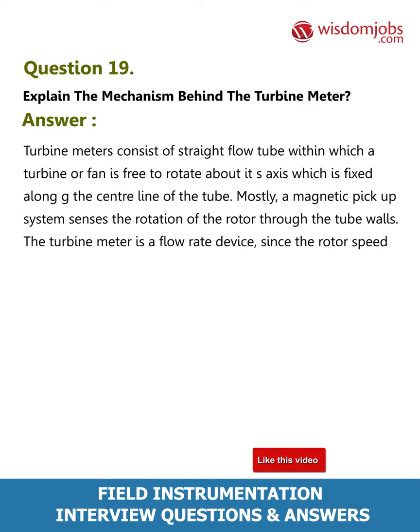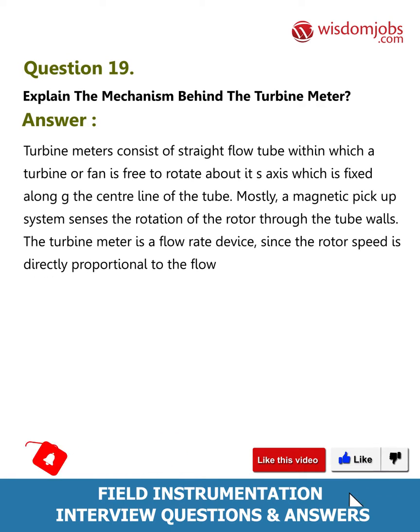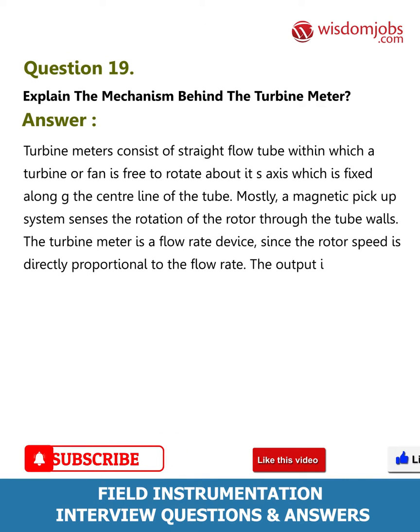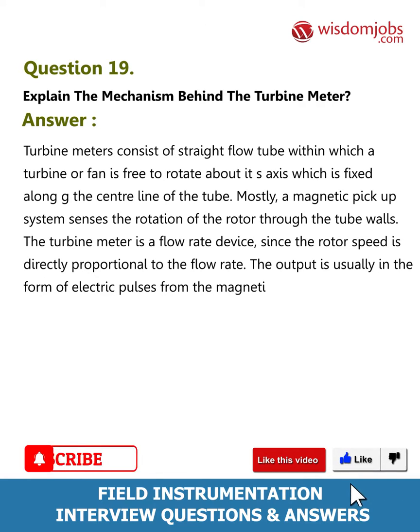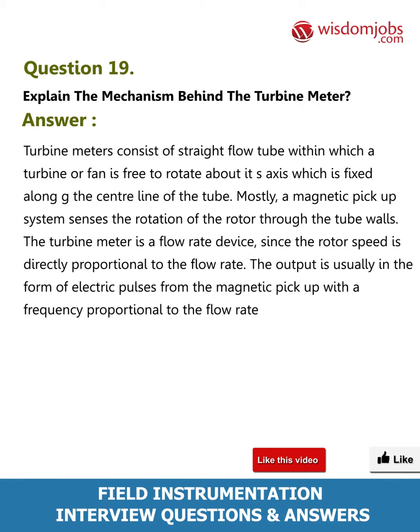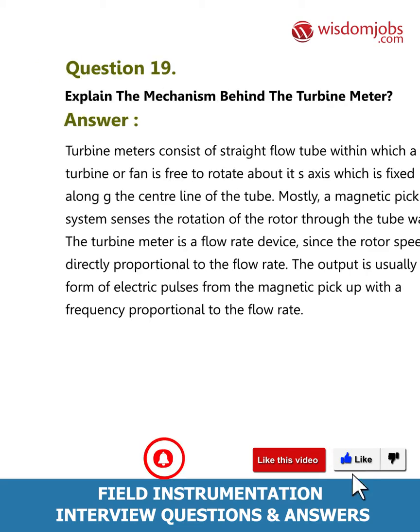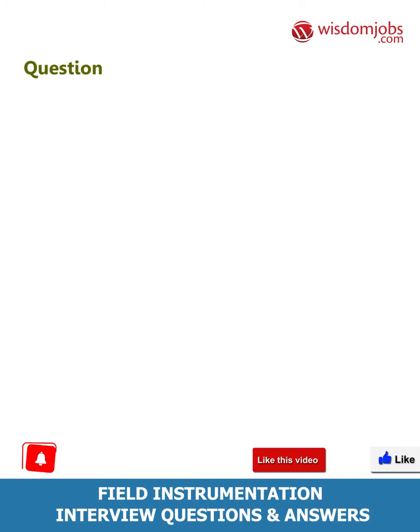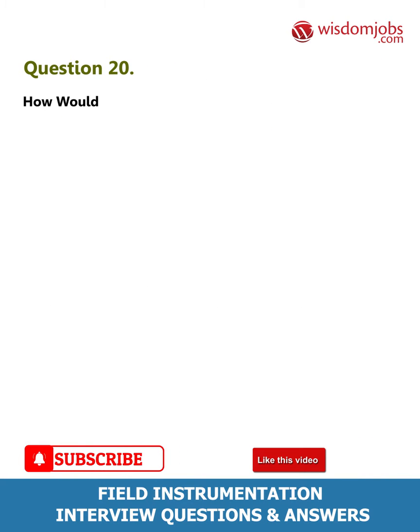The turbine meter is a flow rate device since the rotor speed is directly proportional to the flow rate. The output is usually in the form of electric pulses from the magnetic pickup, with the frequency proportional to the flow rate.